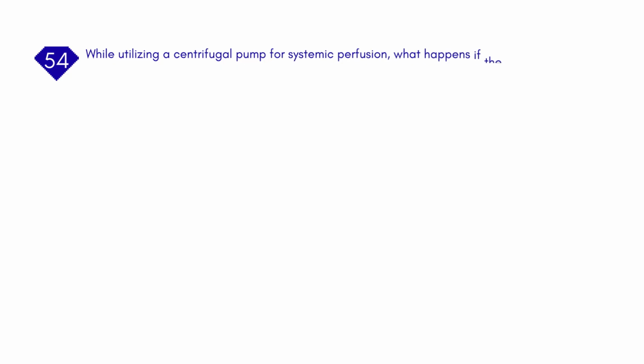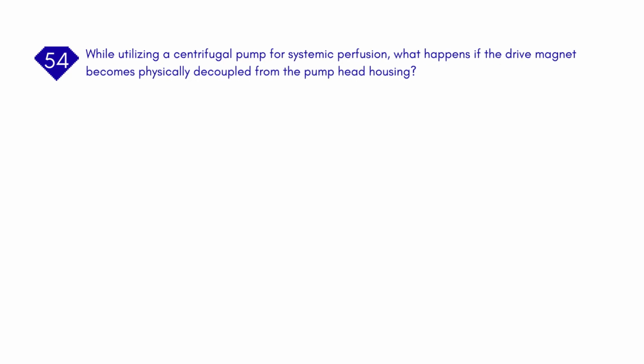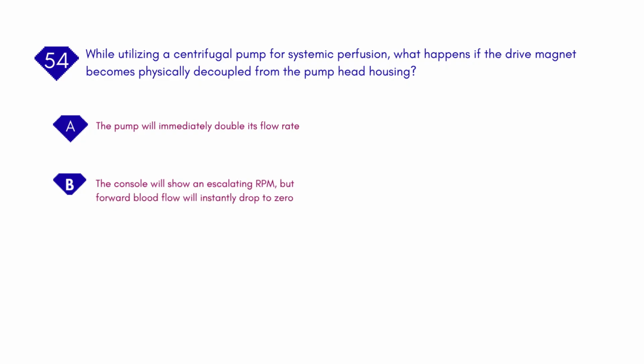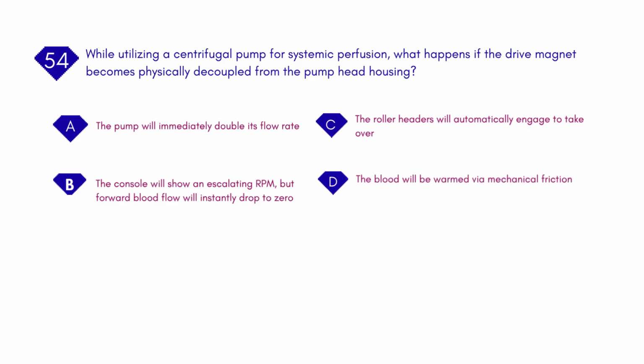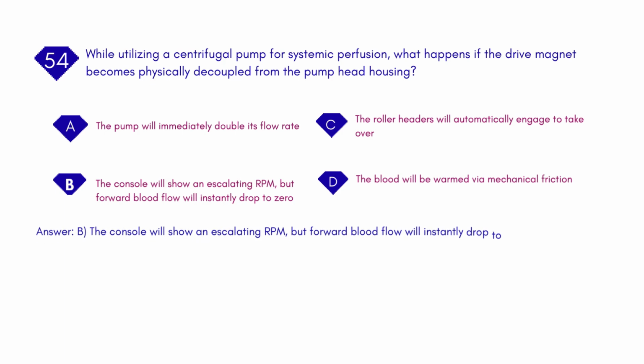While utilizing a centrifugal pump for systemic perfusion, what happens if the drive magnet becomes physically decoupled from the pump head housing? A. The pump will immediately double its flow rate. B. The console will show an escalating RPM, but forward blood flow will instantly drop to zero. C. The roller heads will automatically engage to take over. D. The blood will be warmed via mechanical friction. Answer: B. The console will show an escalating RPM, but forward blood flow will instantly drop to zero.